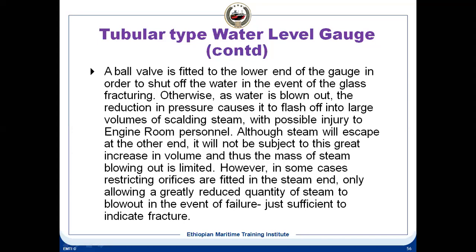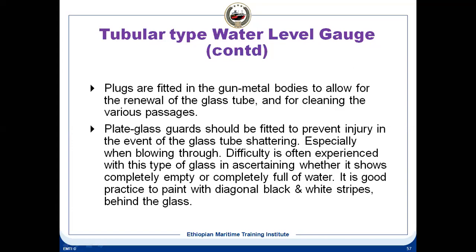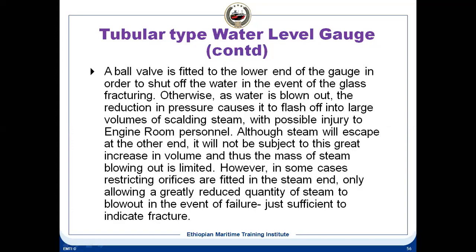However, in some cases, restricting orifices are fitted in the steam end, only allowing a greatly reduced quantity of steam to blow out in the event of failure, just sufficient to indicate a fracture. So that means the glass balls, the metal balls which we were talking about earlier, need not shut off the orifices completely.